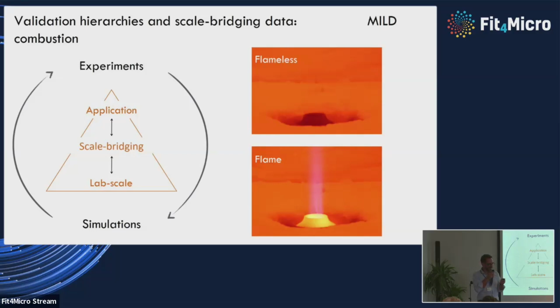When it comes to these new fuels, the first thing I want to do is look at what it means to have a flameless system. I told you the furnace is a flameless furnace, using a flameless burner, and that flameless combustion is very flexible with respect to fuel. But you might think that whatever fuel I put inside, it will be flameless. So let's consider this: what do you think happens if I take the same furnace and inject hydrogen? Would you see flameless behavior or not?